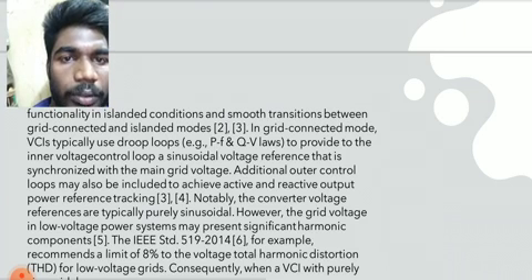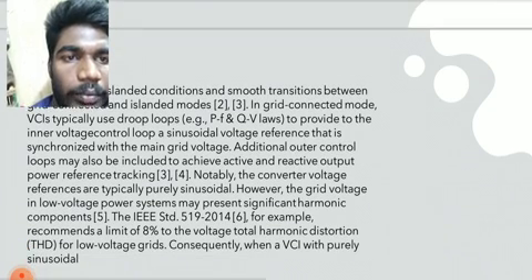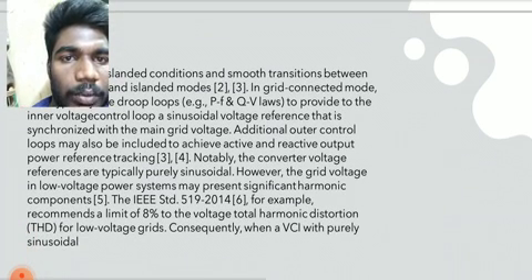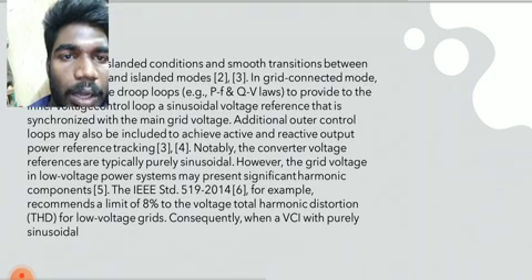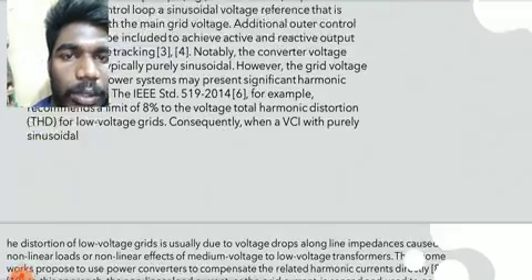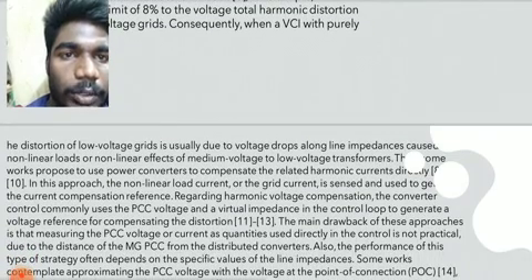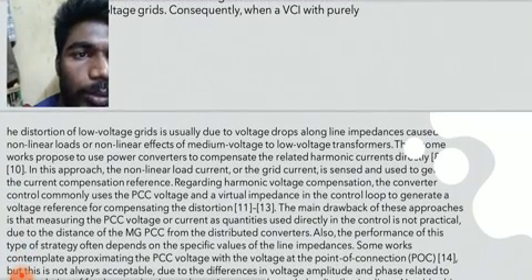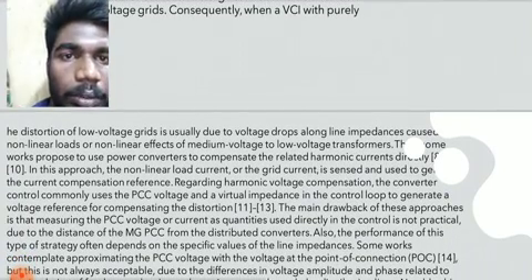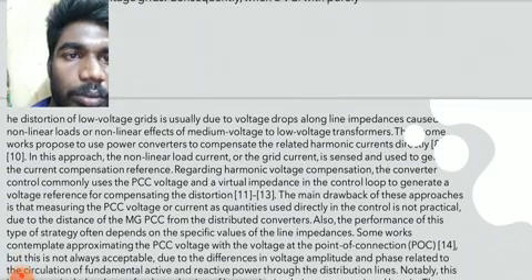Notably, the converter voltage reference is typically purely sinusoidal. However, the grid voltage in the low voltage power system may present significant harmonic components. The IEEE standard, for example, recommends a limit of 8% for the voltage total harmonic distortion, THD, for the low voltage grid. Consequently, when the VCI is purely sinusoidal, the grid voltage is usually distorted due to the voltage drop along the line impedance, nonlinear loads, or the effect of the medium voltage to low voltage transformer.